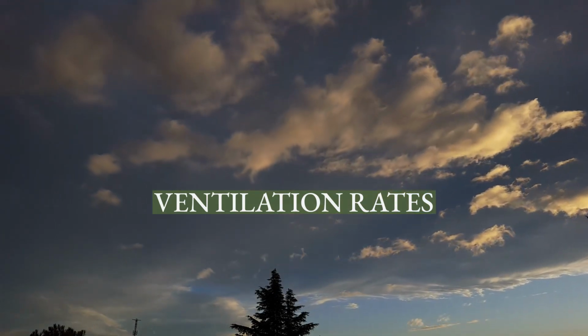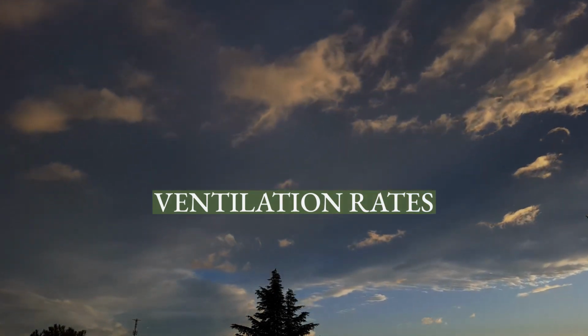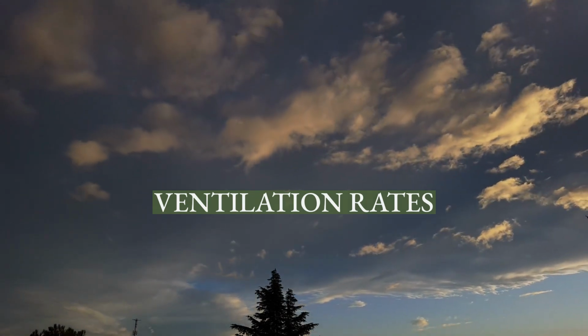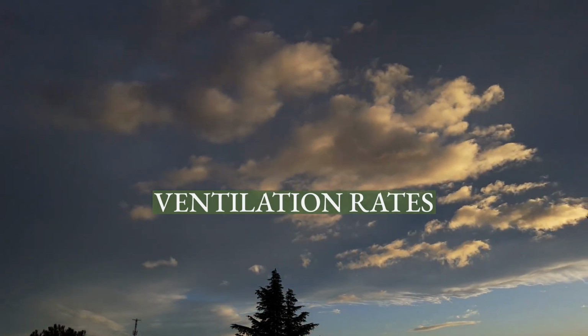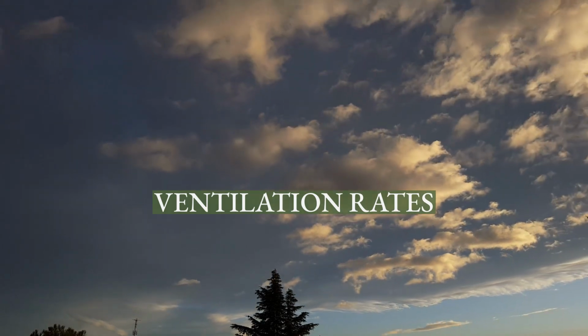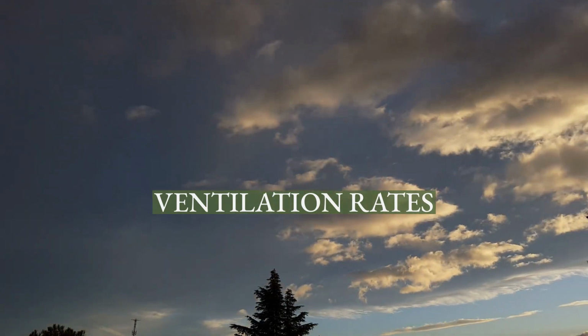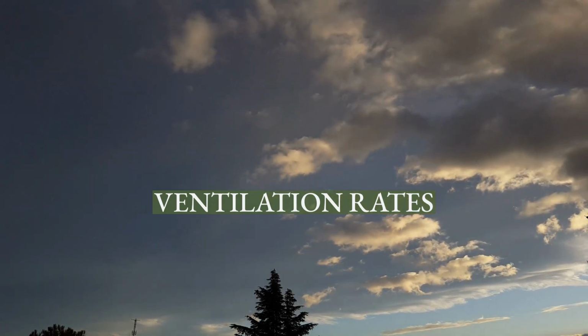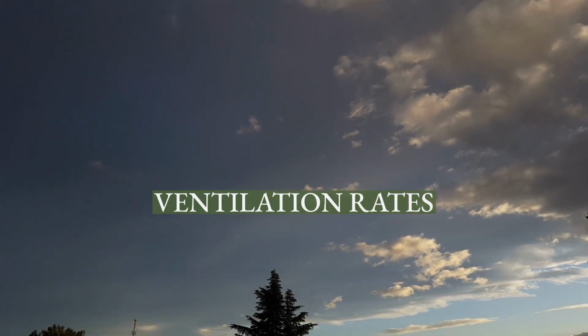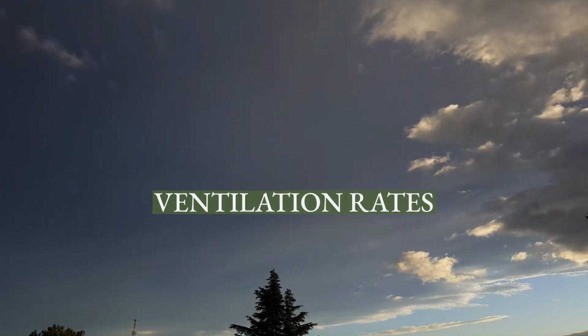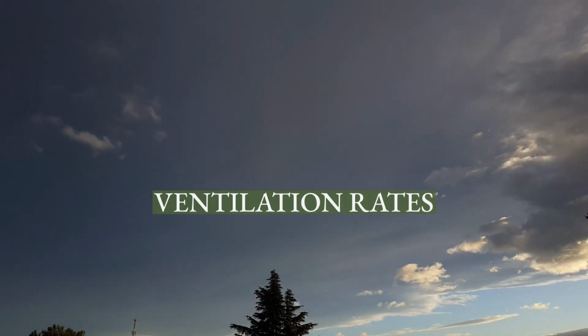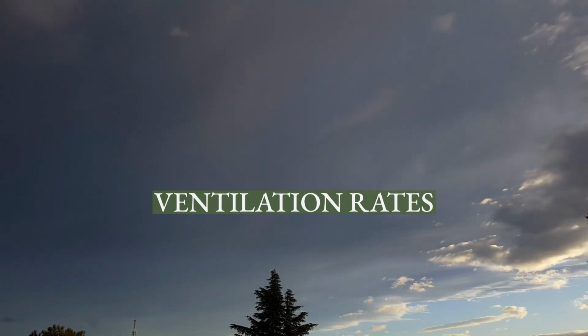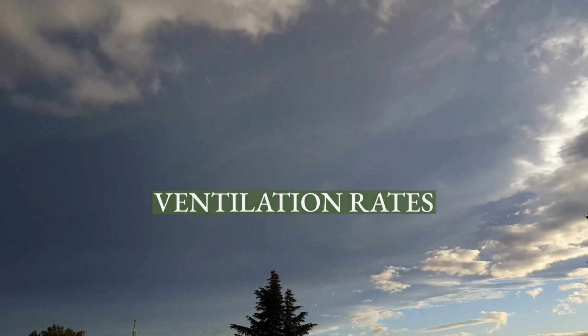P = ACPH × D × H / 60, where P equals ventilation rate per person, in cubic feet per minute (CFM per person) or cubic meters per minute per person. ACPH equals air changes per hour. D equals occupant density, in square feet per occupant or square meters per occupant. H equals ceiling height, in feet or meters. 1 cubic meter per minute equals 16.67 liters per second.